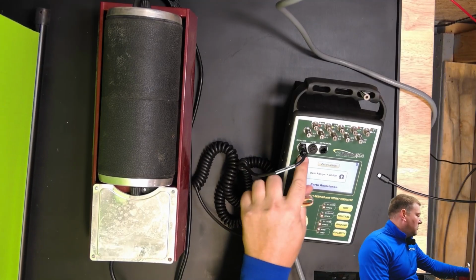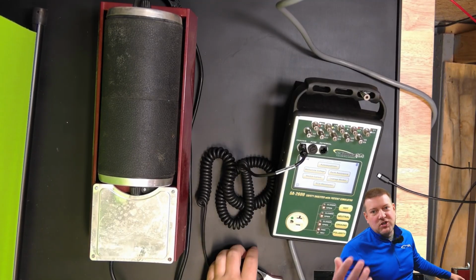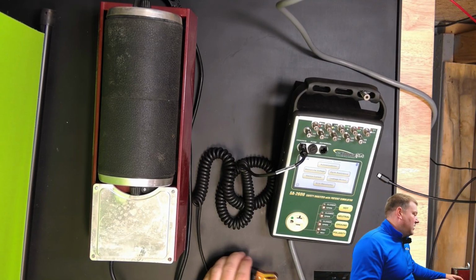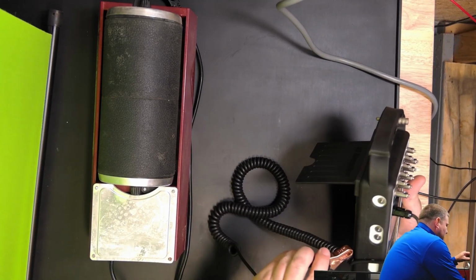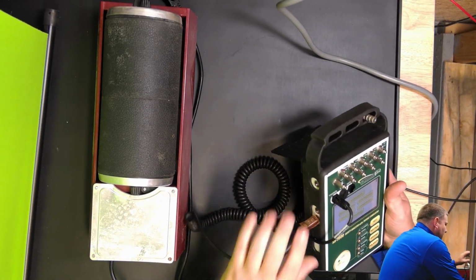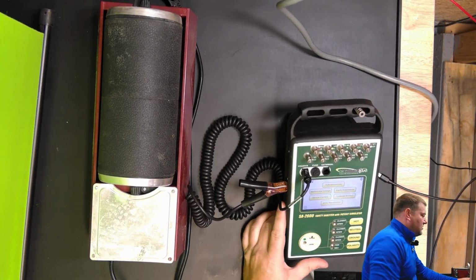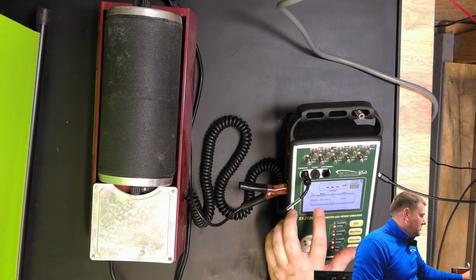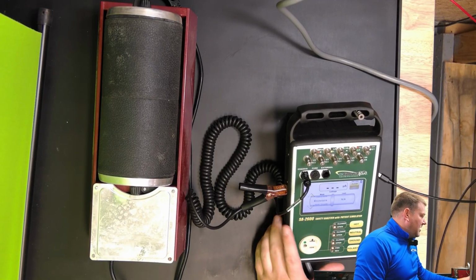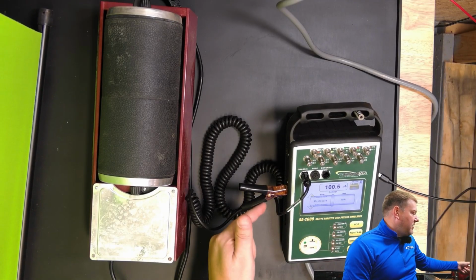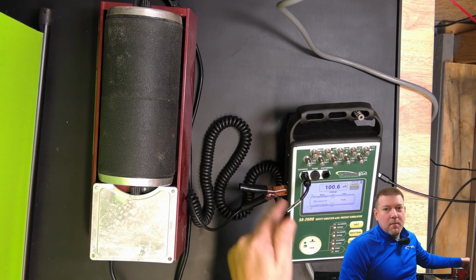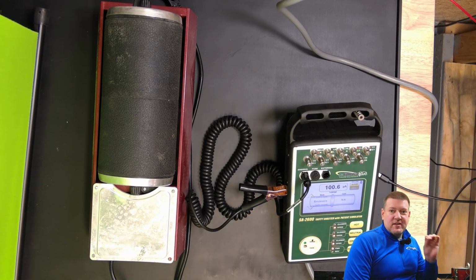Now, the next thing that we should do is test out the calibration of the meter. The best way to do that on electrical safety meters is they usually have a lug for testing leakage. So we are going to go into leakage modes, and I'm going to set it to enclosure leakage, and I have it connected to the 100 microamp output stud. So this is a calibration stud.